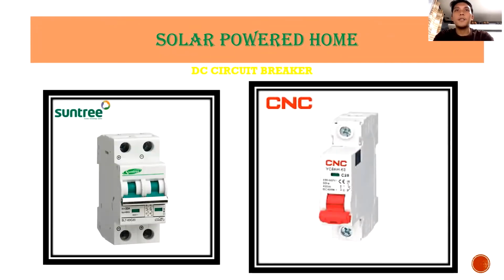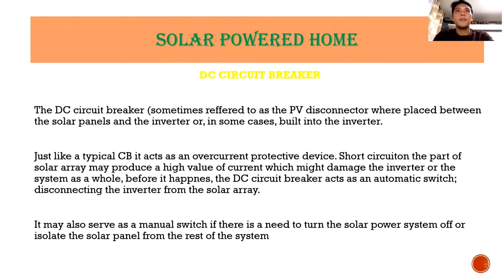This is the example of the DC circuit breaker. The DC circuit breaker, sometimes referred to as the PV disconnector, is placed between the solar panel and the inverter, or in some cases built into the inverter. Just like a typical CB, it acts as an overcurrent protective device. In a short circuit, part of the solar array may produce a high value of current, which might damage the inverter or the system as a whole. Before that happens, the DC circuit breaker acts as an automatic switch, disconnecting the inverter from the solar array.